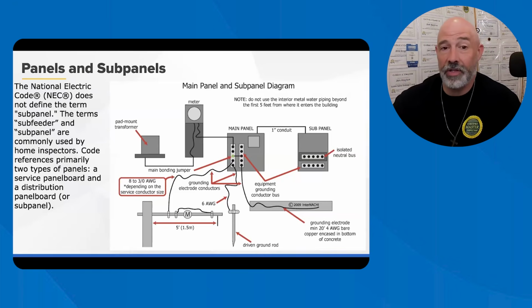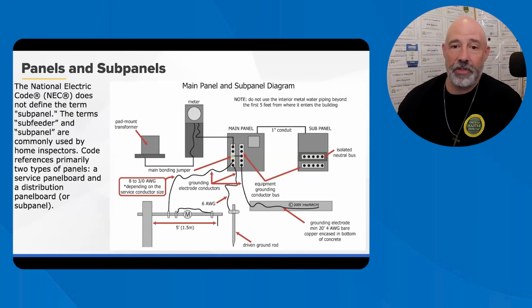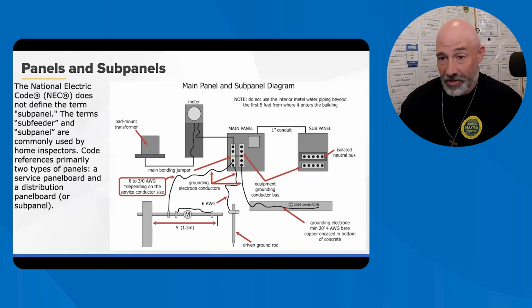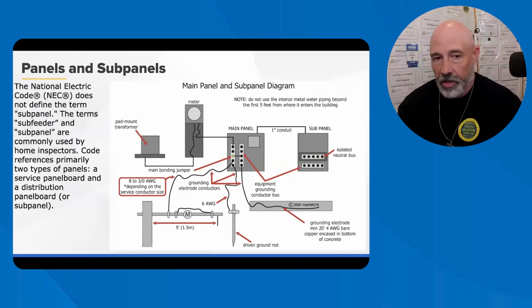And in the sub panel, the neutral and grounding conductors must remain separated. I keep saying that it's disconnected there. The only exception to this is existing detached structures with no metallic path existing between the structures. In this exception, a connection between the grounded conductor and the metal case via a bonding jumper is permitted, according to the 2008 NEC. This is not allowed in new construction, just FYI. So in many cases, a 4-wire feeder to the detached structure is required in order to isolate the grounded conductors from equipment grounding conductors. So things have changed over the years.